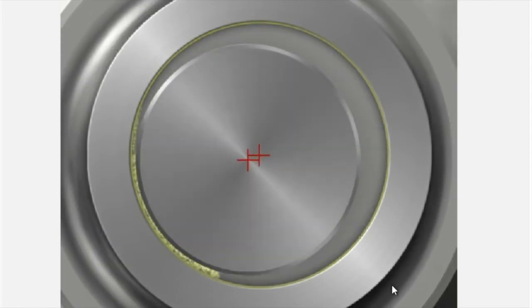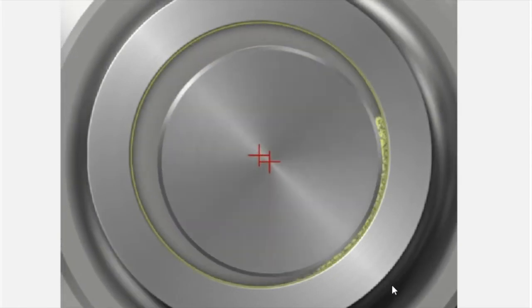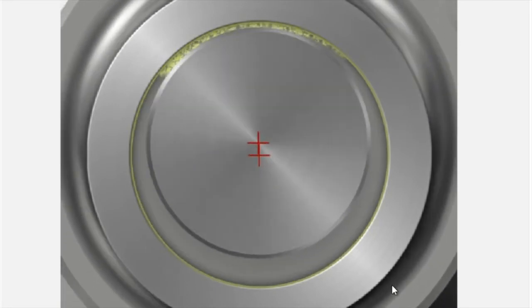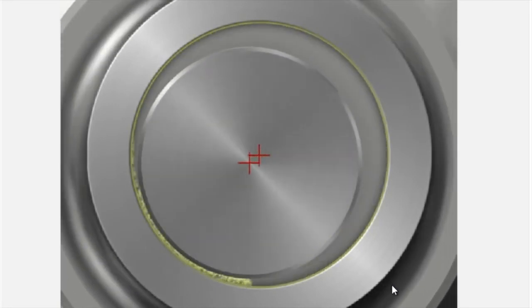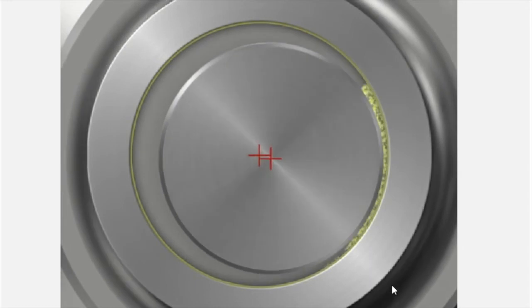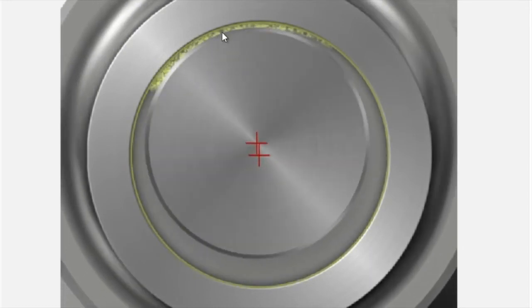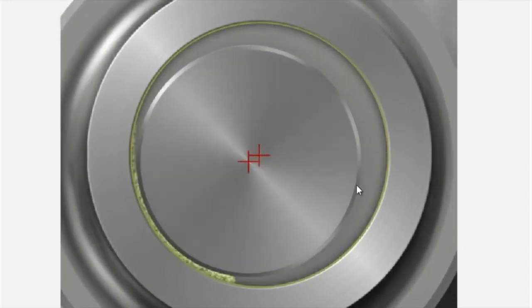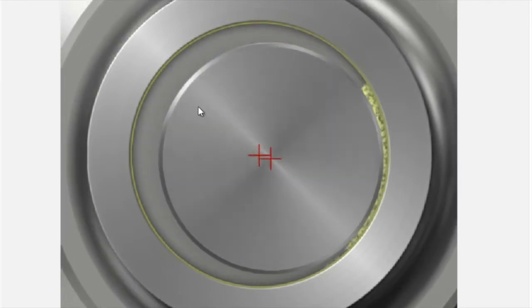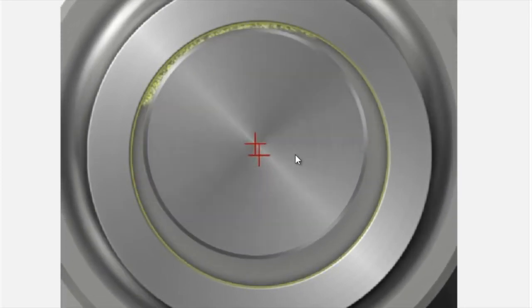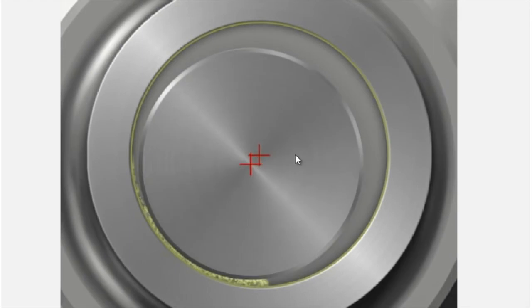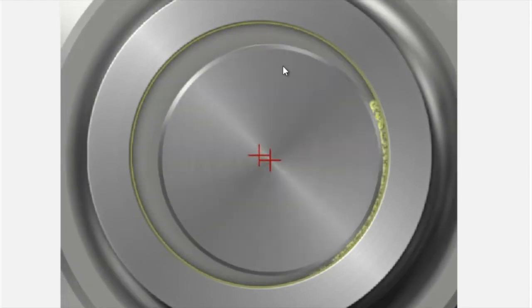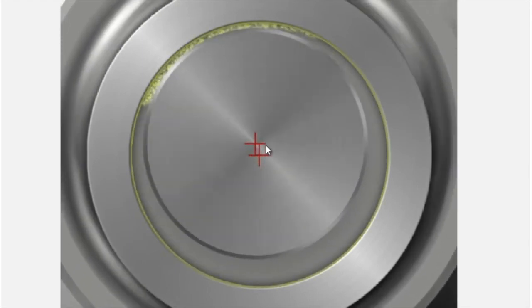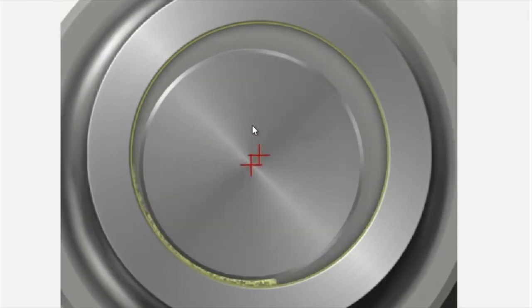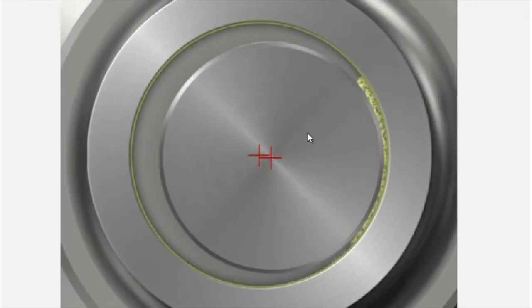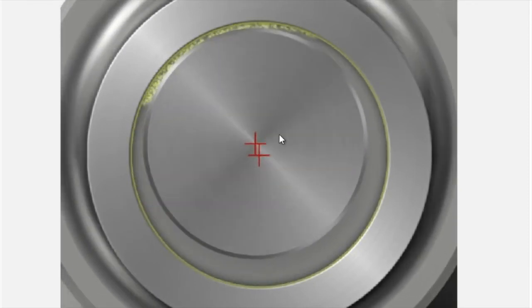What we'd like to be able to tell is just what is the rotor doing? What is the journal doing within that bearing? In this instance, we have oil whirl. This wedge of oil is actually following the shaft around as it moves in this big wide motion. It's using up all of the clearance that's available, hopefully still keeping that wedge there, but this is quite high vibration. It can't be any higher at this particular location. It can't be any more motion because it would start wearing away the bearing.